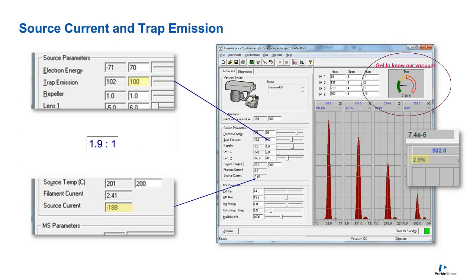This is just where you can see on your tuning page. Your tune page tells a lot of things about how your system is behaving. If the tuning algorithm is not running like it consistently usually does, that's indicative of a problem. You should be getting the same numbers after the algorithm is done.